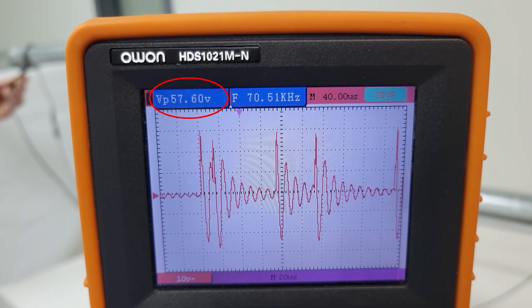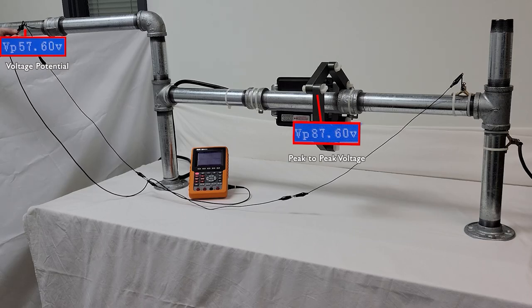Note that the voltage potential will be lower than the peak-to-peak voltage at the unit due to the distance. Ideally, you should see a few volts throughout the system. If the voltage potential measurement is under a volt, you should consider installing an additional HydroFLOW unit.